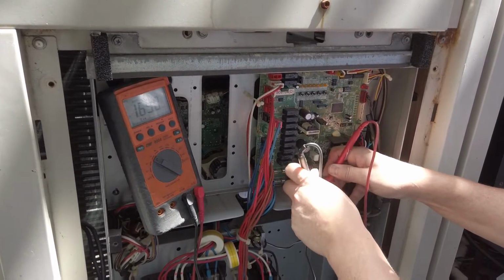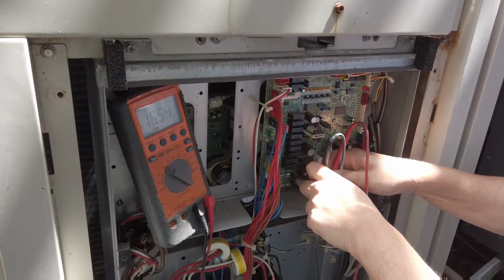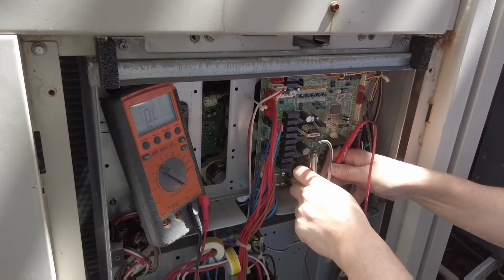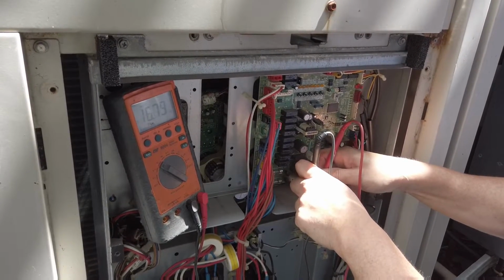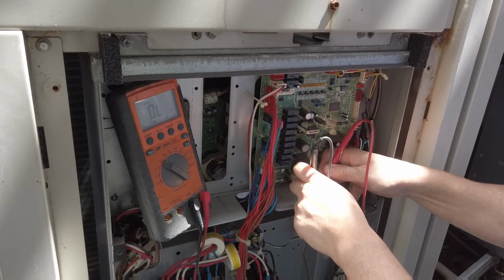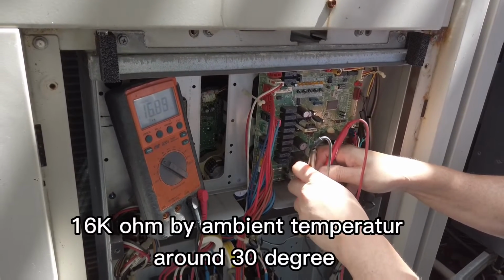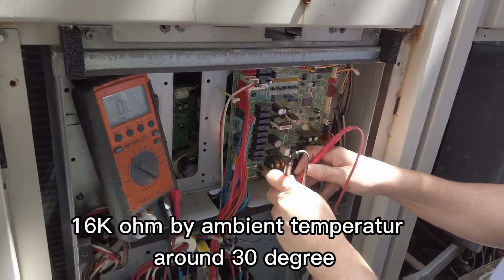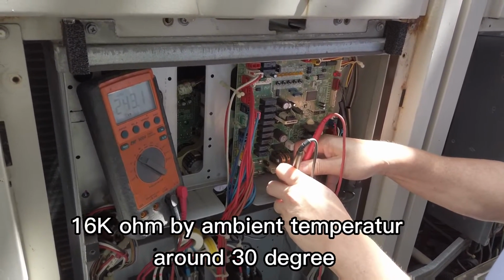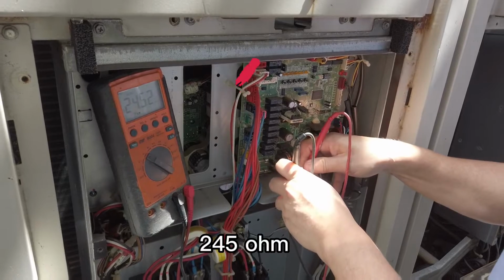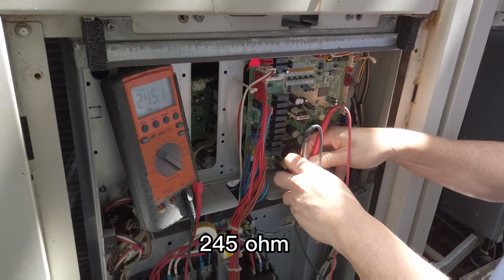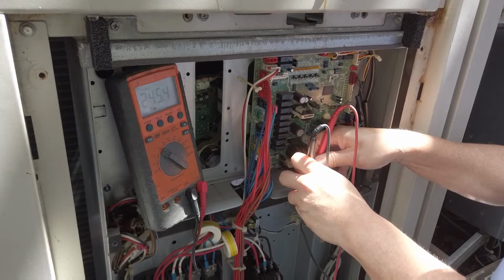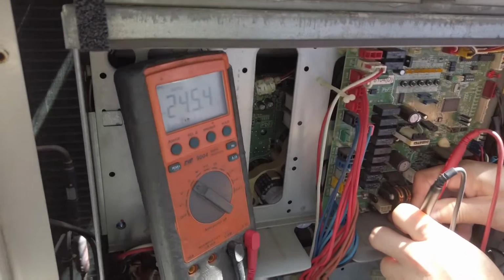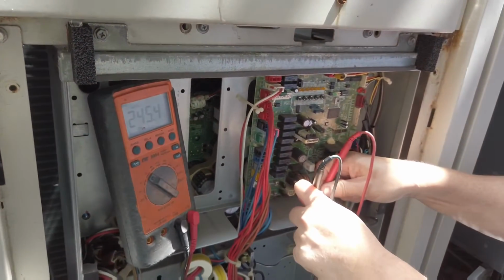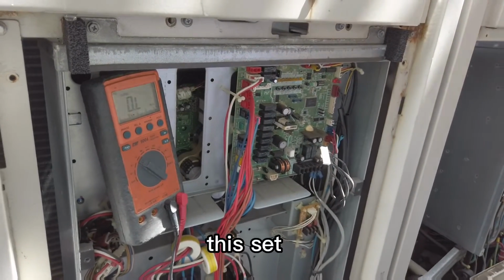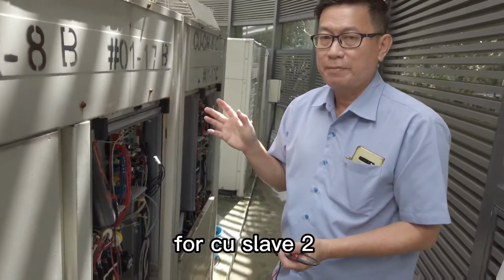1.6 kilo ohm. It should be 16 kilo ohm at an ambient temperature around 30 degrees. This one is short circuit, the thermistor, 245 ohm. Okay, 245 ohm. Okay. This set has two thermistors out for CU slave 2.